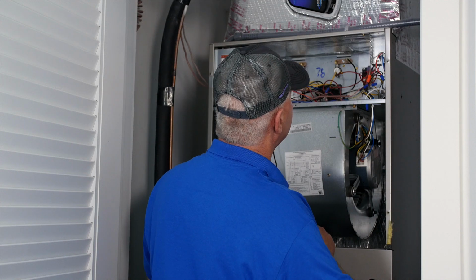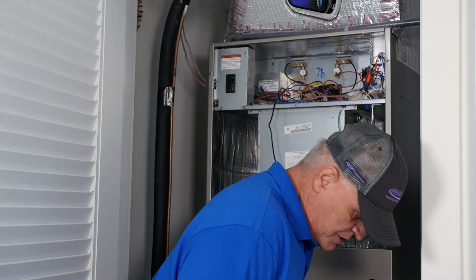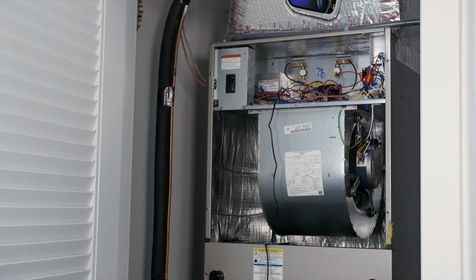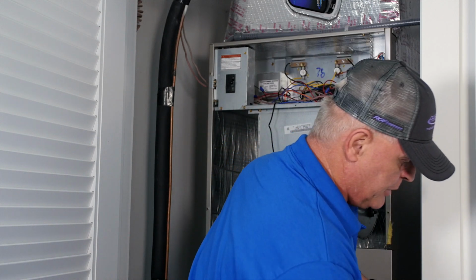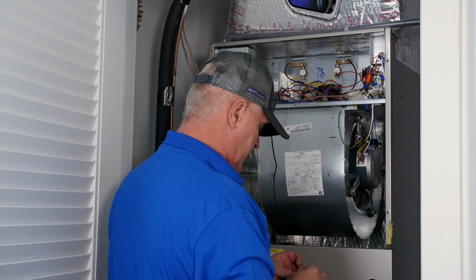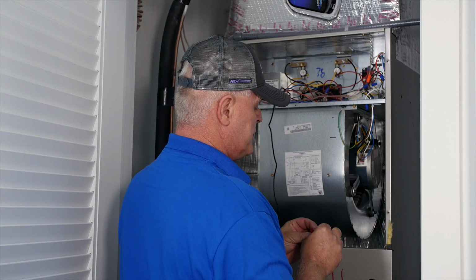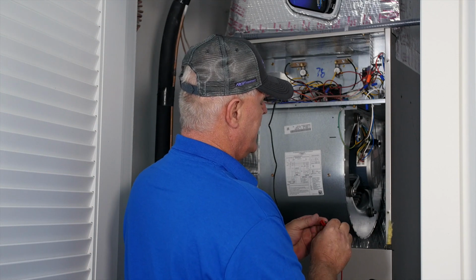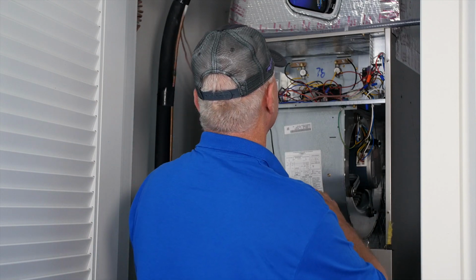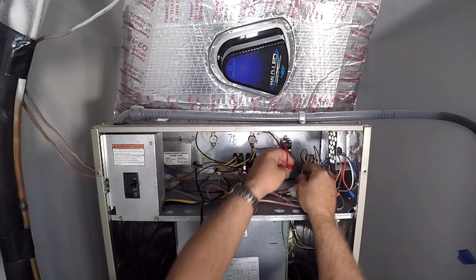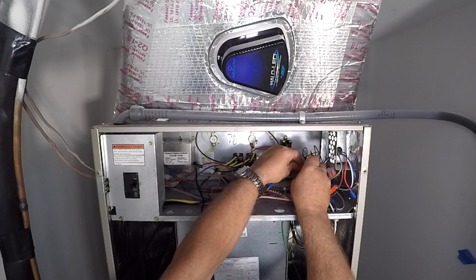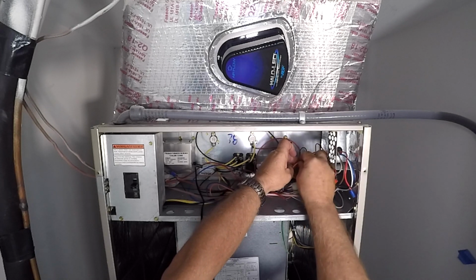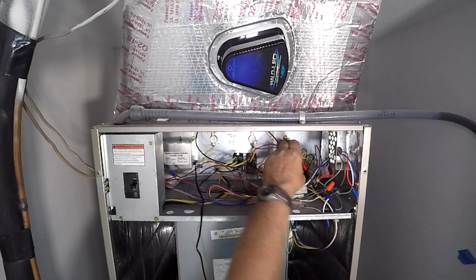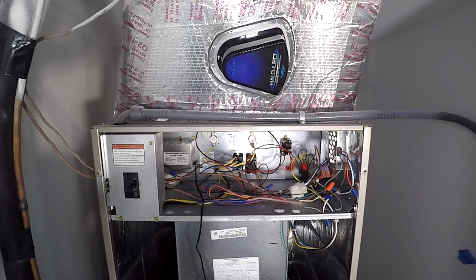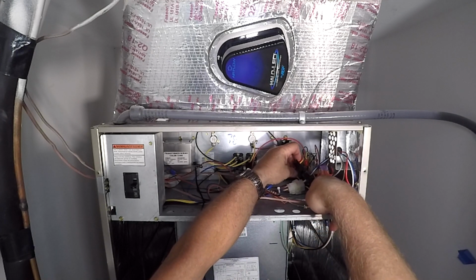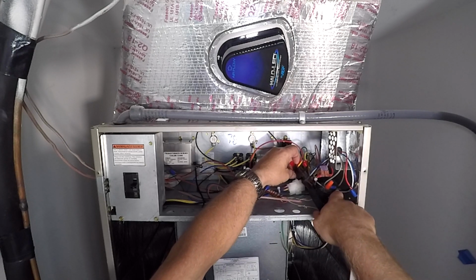Now, our terminal 2 on this unit is going to be connecting to the other side of the line voltage, so it will turn on when the relay is energized. Again, I am not going to cut any of the wiring in the air handler. I am going to use another one of my little line taps here. And that, on this particular unit, is going to come to the incoming to the existing transformer on the yellow on this particular unit, but every unit is possibly going to have a different color there. So that now you have your full 240 volts to feed this unit, whether it's in heat or cooling.